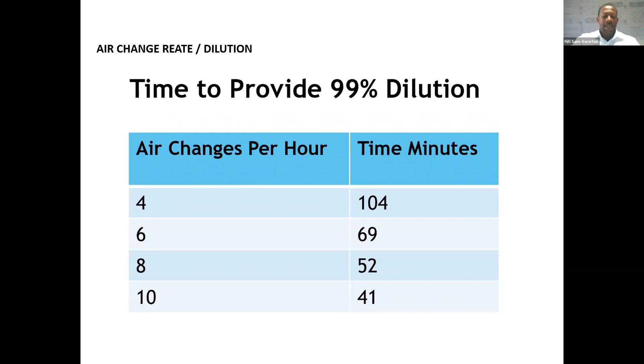So with what we have on our screen now, if an infected person enters an air-conditioned space and coughs, releasing 100 pathogens into the air, and we have 4 air changes per hour, it will take 104 minutes to clear the room of pathogens, leaving only 1. If we increase the air change per hour to 6, we reduce this time almost half, that is 69 minutes. Then when we get to 8, it doesn't change much. Then 10, also not that much from the previous. So 6 air changes per hour is pretty much the standard for dilution.